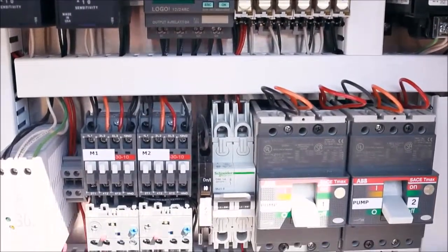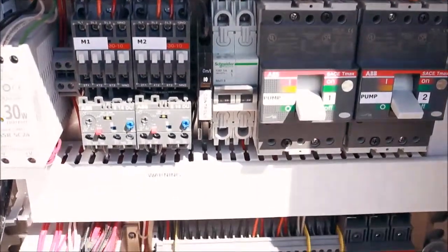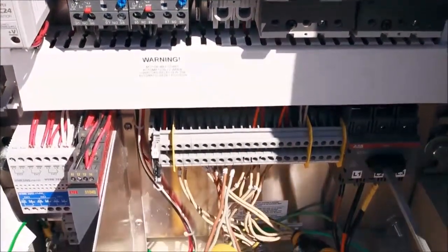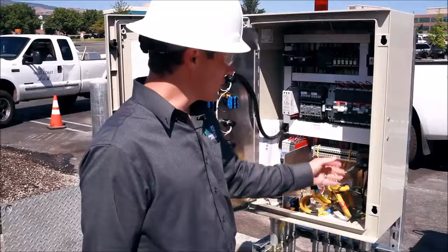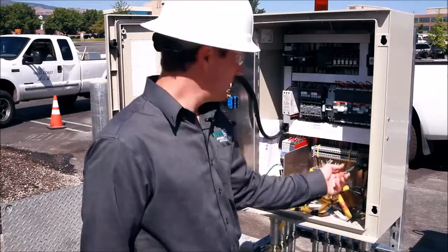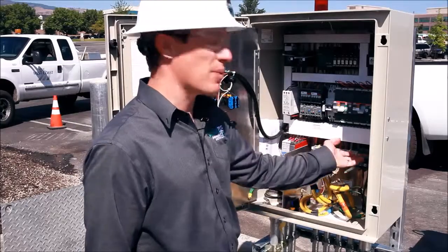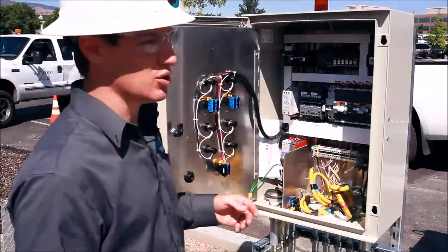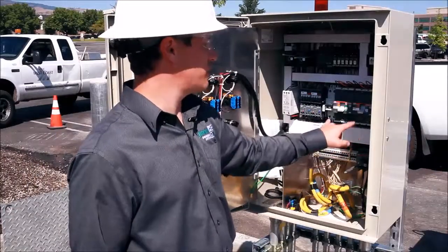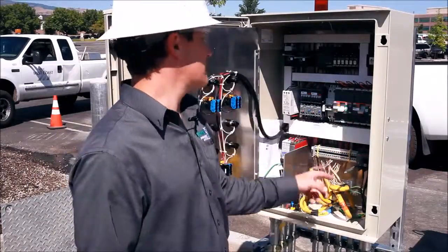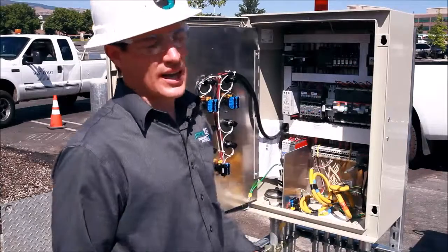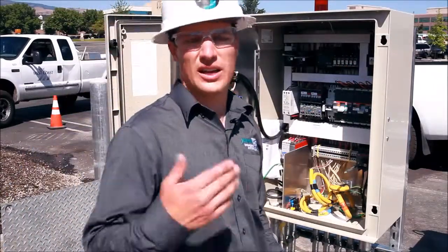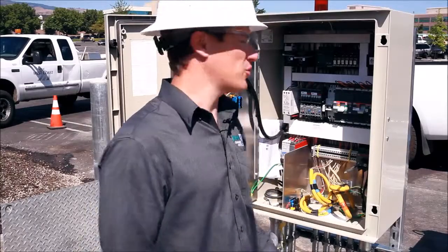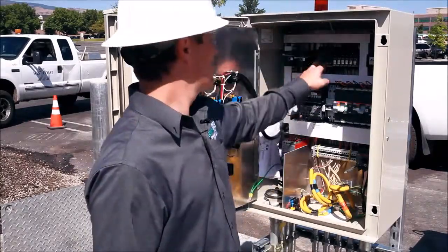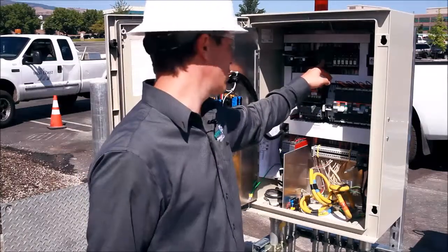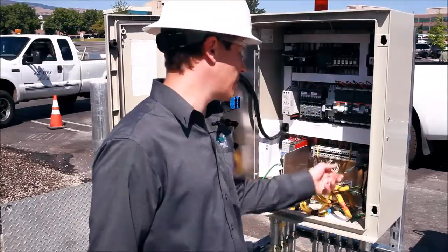So once we're inside the panel, we'll basically follow the flow of energy and talk about the different components that are supplied with a typical Jensen precast pump station. So the inline voltage from the power company is coming in here. This is our main disconnect. It's in the off position. From there, the power travels and is split to two locations. The first location is split to pumps 1 and 2, high voltage, and then it's also sent to a transformer up here in the right corner. And the transformer converts a leg of the power to single phase 120 volt power. That's to run the light, our programmable logic controller, and some of the other low voltage components inside the panel.